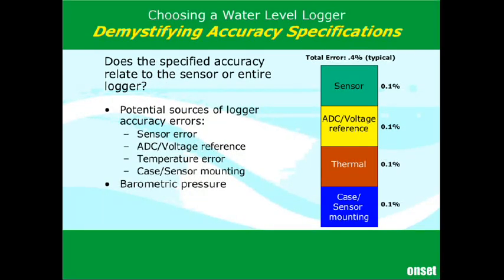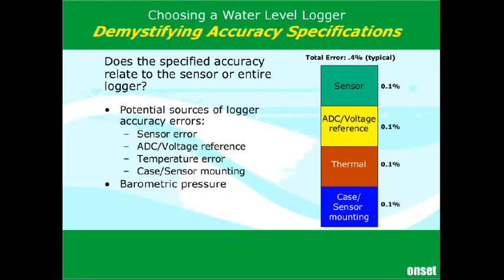Let's talk about specifications. Does the specified accuracy relate to the sensor or the entire logger? Oftentimes, when you review specification sheets, you'll find that the sheets talk about sensor accuracy instead of the whole logger accuracy. So it's important that you understand what you're reading and evaluating. There are additional errors beyond the sensor: case and sensor mounting errors, thermal errors, and logger circuitry errors. It's important to consider this whole pressure logger error when selecting your logger.